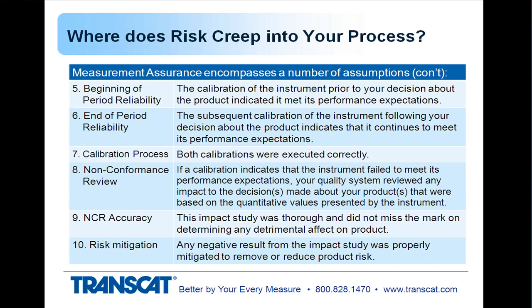And then the accuracy of that nonconformance review. How thorough is it? Did it miss the mark on making sure that it evaluates whether those errors in the instrument actually had an impact on where it was being used? And then risk mitigation. Any negative result from the impact study, and how that's mitigated to remove or reduce risk in your product.